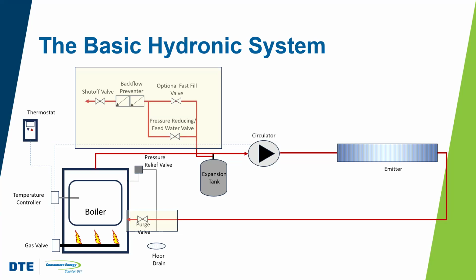So for example, when air is vented out of the system during service or startup, we want to be able to allow that to be expelled. The makeup water system also includes a backflow preventer. This does exactly what the name says, right? It stops the water that's now in your system from flowing back into the municipal potable water system, right?